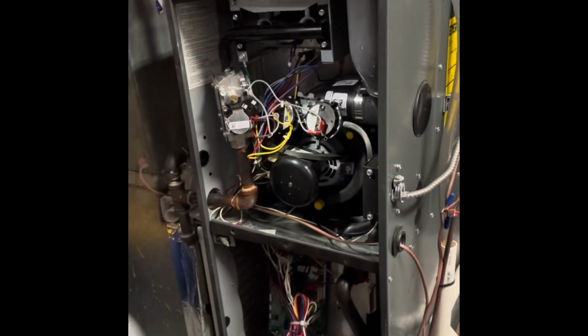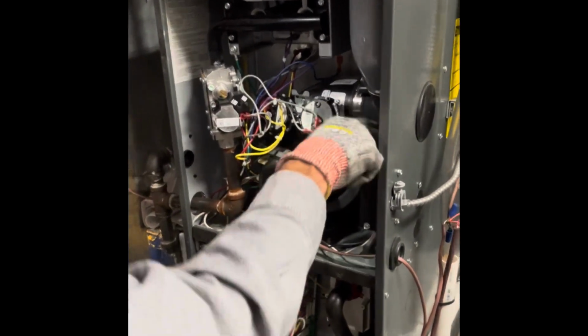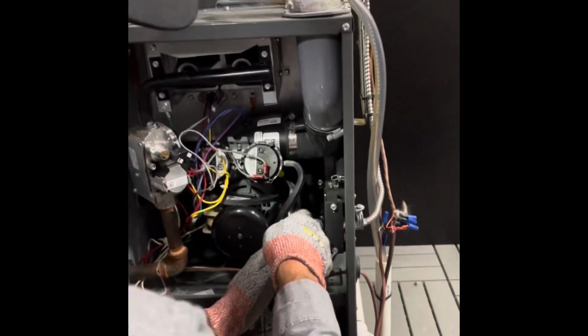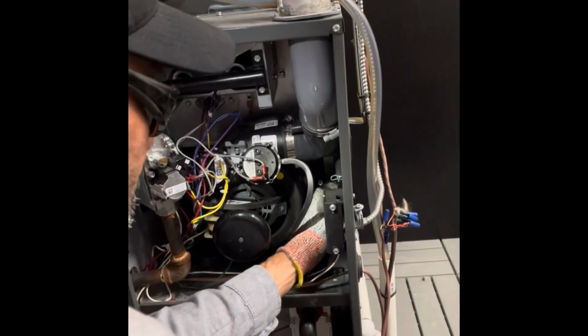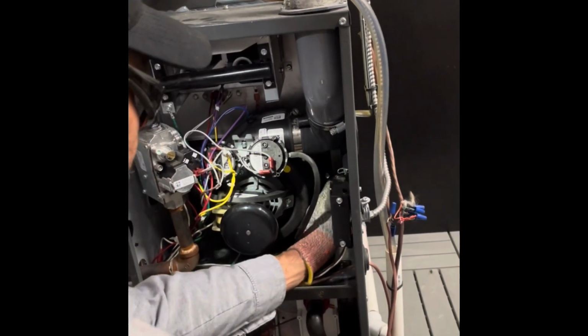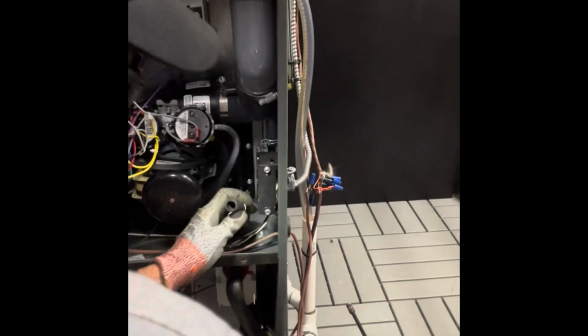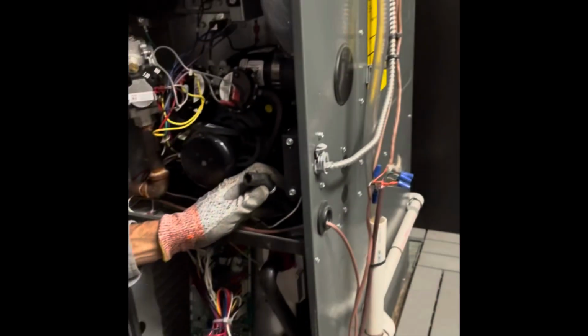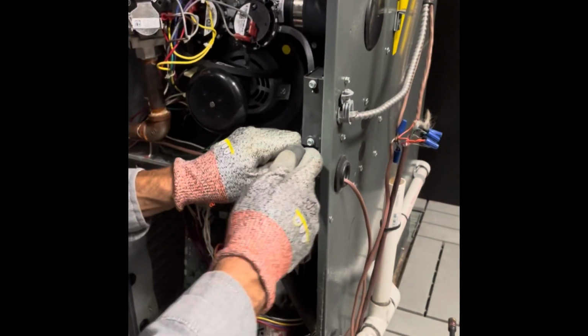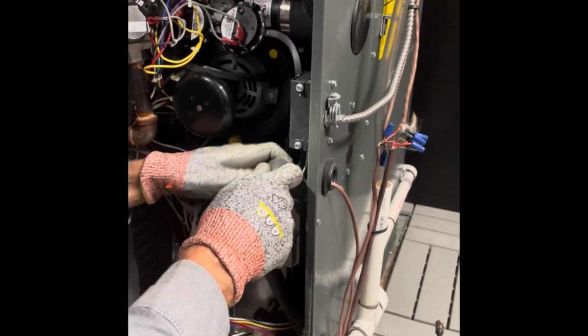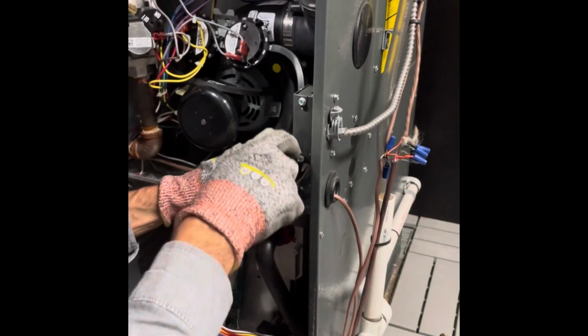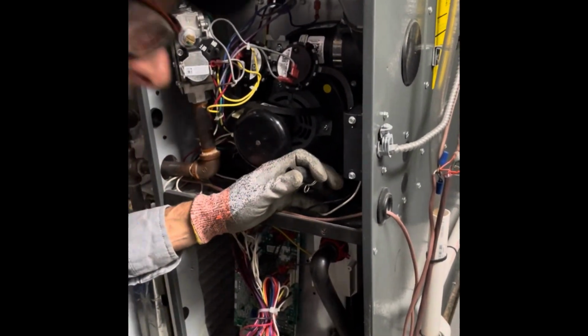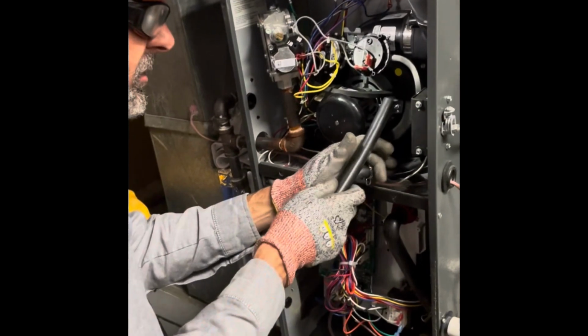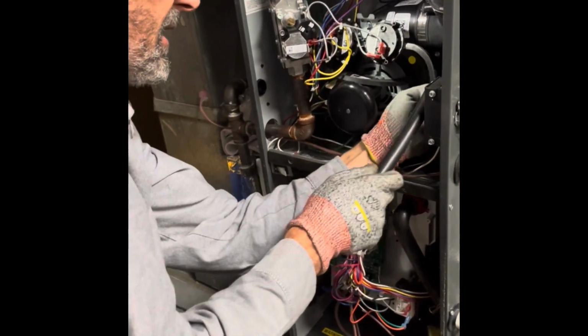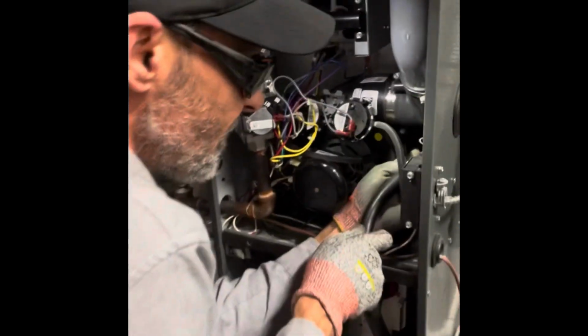Next thing, I'm going to clear the two thicker condensate hoses. So there's one on the right, that's for our venting system. And to remove these, this clamp's not really on there tight, we just slide it down and pull the hose off. I'm going to get my little adapter hose. I just want to blow a bit of air in here to make sure that this line isn't plugged. So that one is clear. Now I'm going to take my other adapter hose and blow air just the way I did in that hose, but in this actual fitting. These are going to plug up. It's usually at the fitting where they'll plug up.